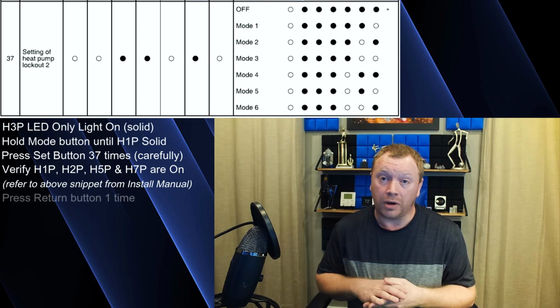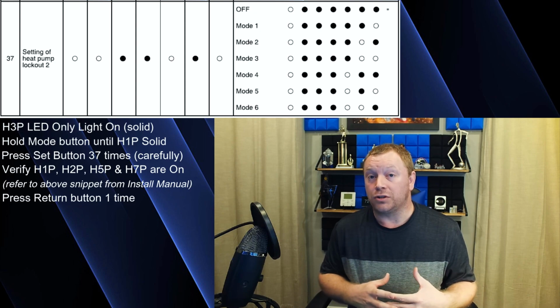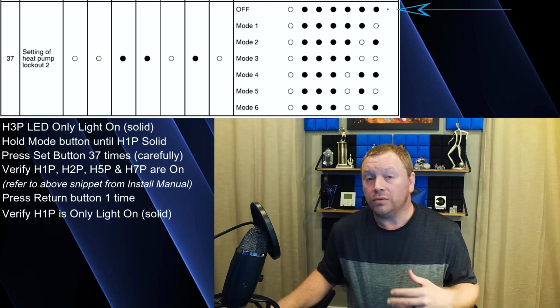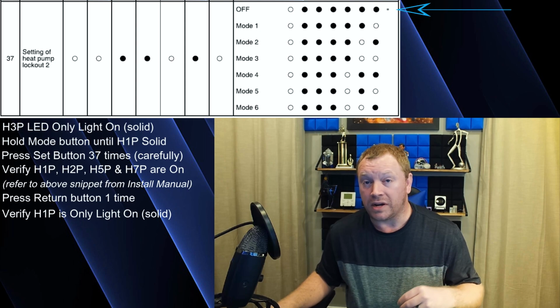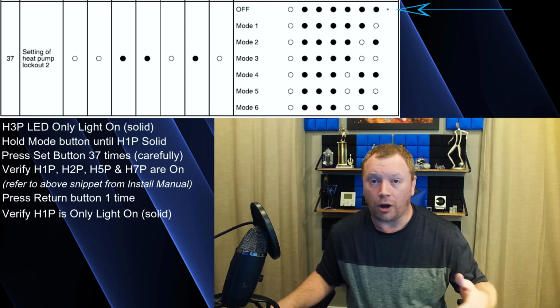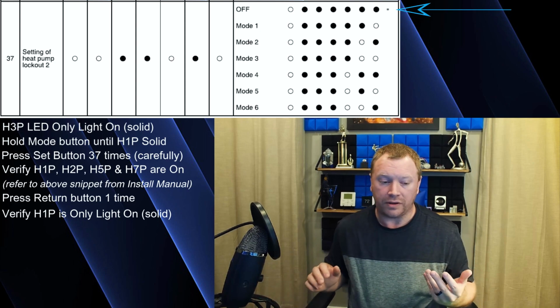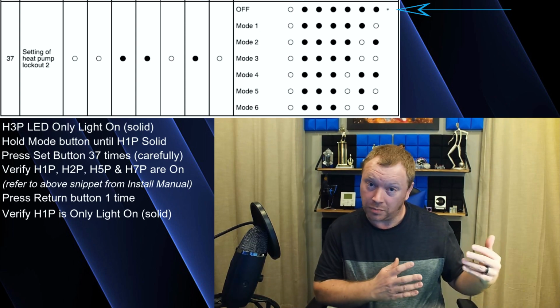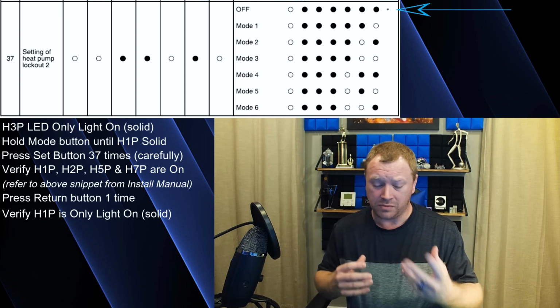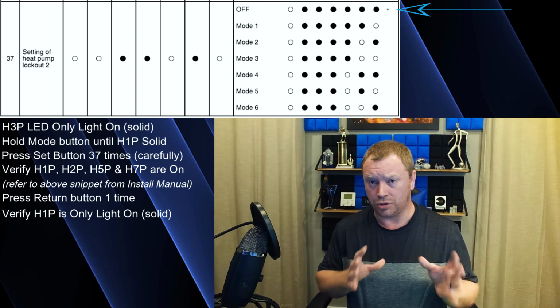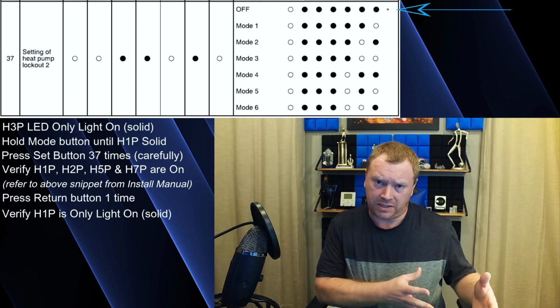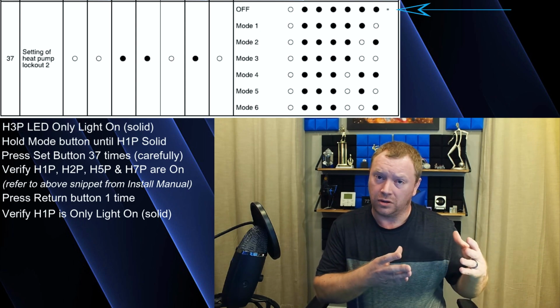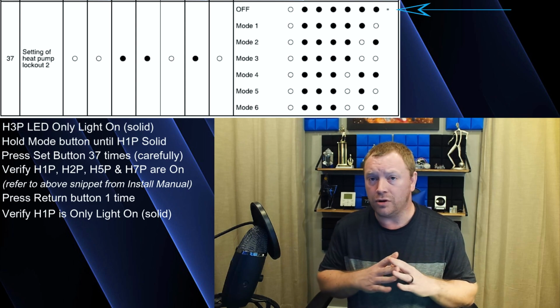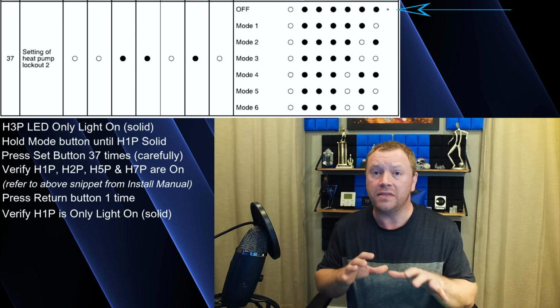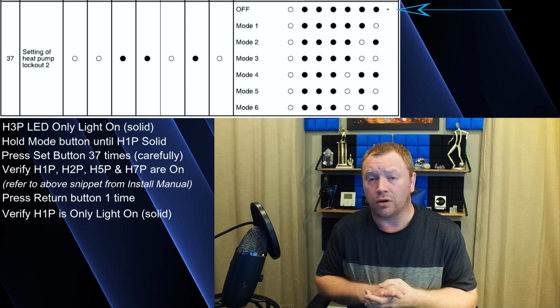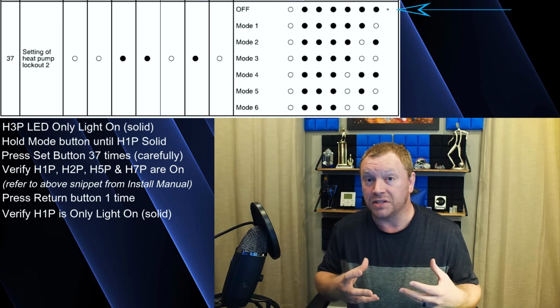Once you verify that you are at 37, you need to go into that setting. And so you press the return button 1 time, and now you're going to have H1P solid. Now, the only reason that H1P is the only light on right now is because the default option is option 0. Well, if I have no lights on except for H1P, that is a value of 0. But sometimes folks will get confused because they'll think, oh shoot, did I press the wrong button? And now I'm back to the beginning of service mode 2. As long as you pressed that return button 1 time, no, you're not pressing the wrong button. You're in that setting, but none of the other lights are on because the current option is 0.